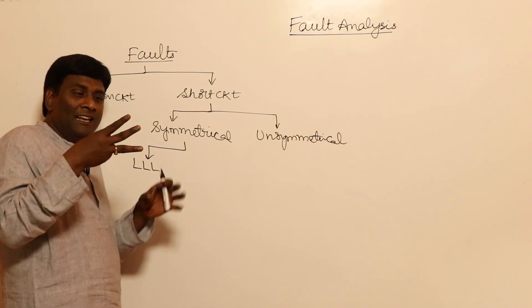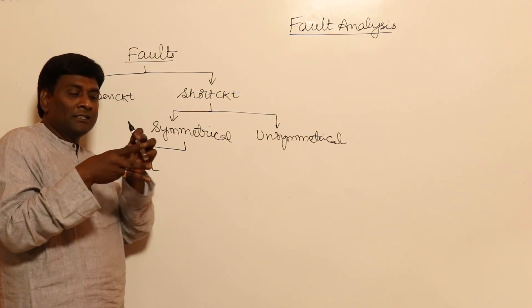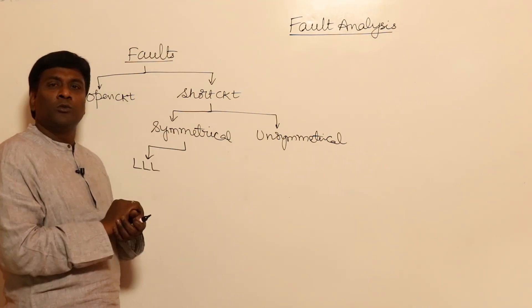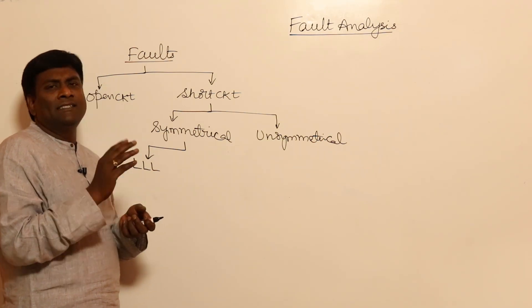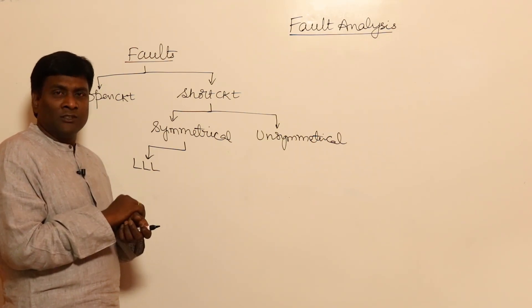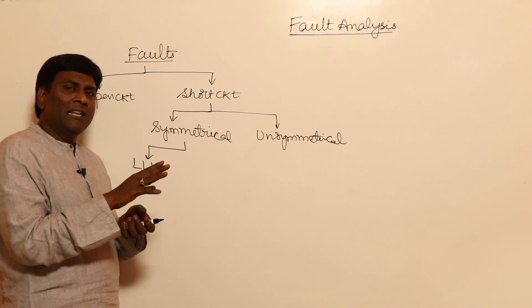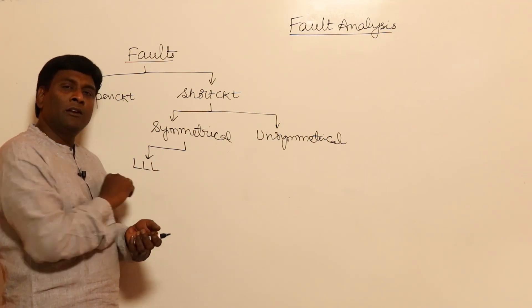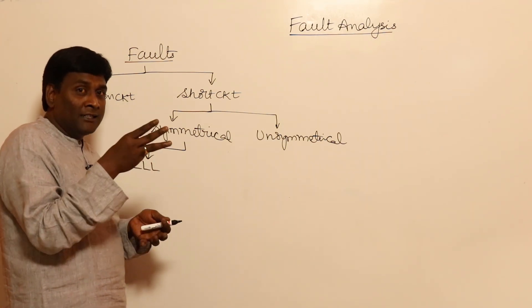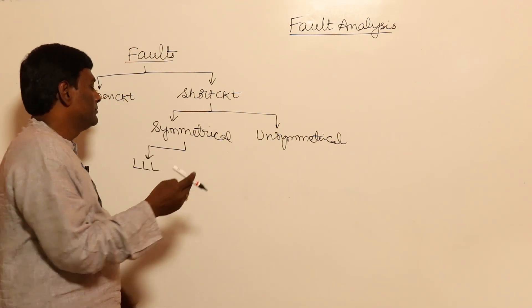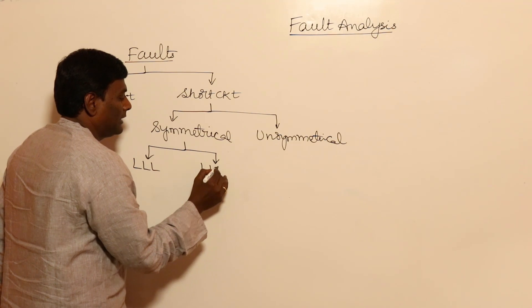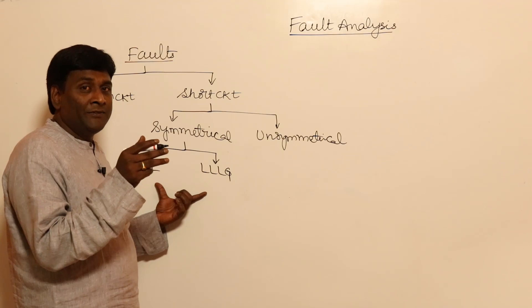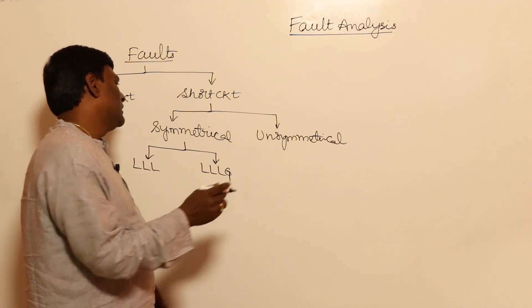In symmetrical faults, examples include the triple-L fault where all three lines are short-circuited. Although DC offset will be different immediately after the fault, except for DC offset all three phases experience the same conditions. Another type is the L-L-L-G fault where all three lines are short-circuited with the ground. Both are symmetrical because all three phases experience the same conditions.